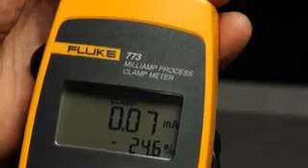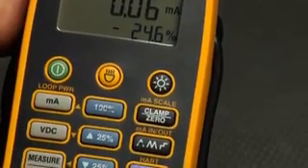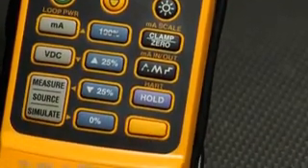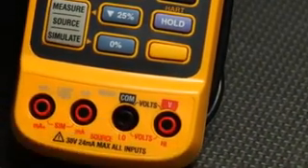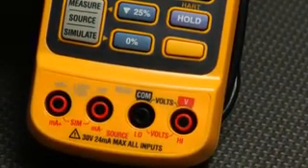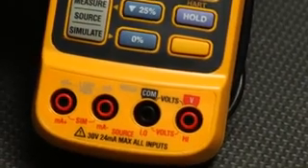The 773 is designed to make finding bad 4-20 milliamp signals fast and easy. Once you find a bad milliamp signal with the milliamp clamp, the next troubleshooting tool, a milliamp source, is already in your hand built into the 773.